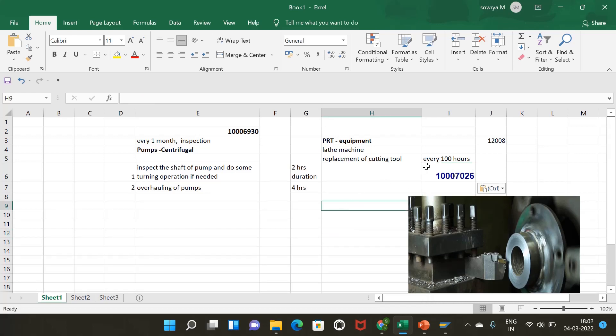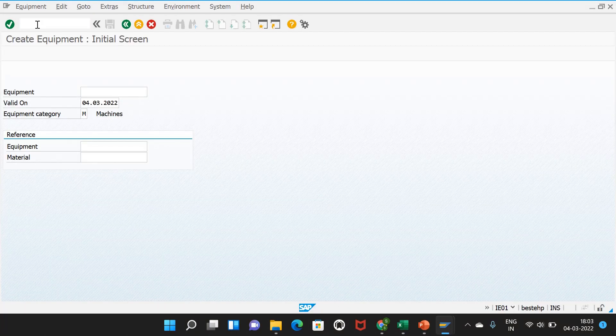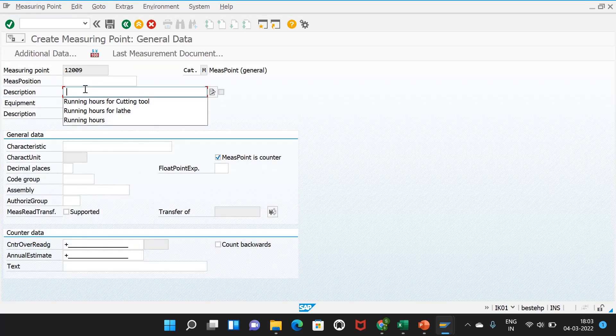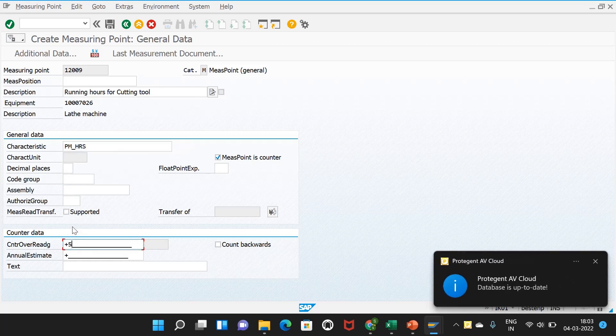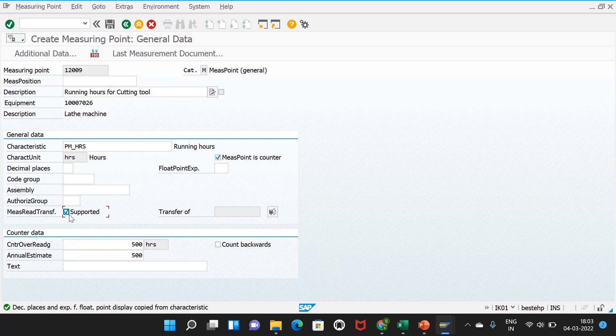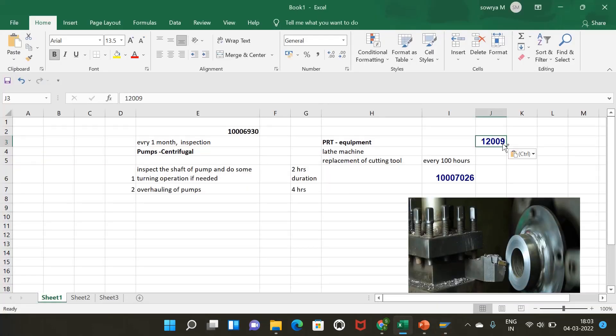Since we are talking about measuring points for this lathe machine, we need to create one measuring point for it. I enter the equipment number of the lathe machine. The measuring point category is general and it is a counter. The description is 'Running hours for the cutting tool' and the characteristic is PM_HOURS. The counter reading is 500 and the annual estimate is also 500. Measurement reading transfer is supported. I save this, and the measuring point created is 12009.